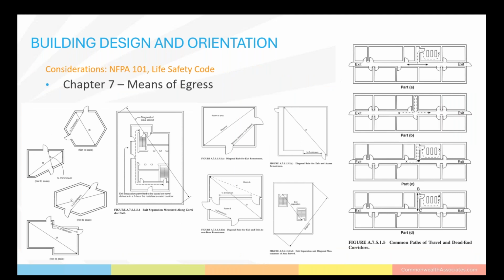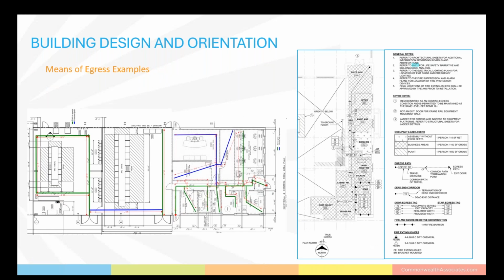Also mentioned earlier, the NFPA codes for life safety. Those basic codes from Chapter 7, means of egress, that need to be met are safe and quick exiting of the building. Exits must be located in accessible areas. Egress must be properly shielded from fire and smoke, ensuring occupants can safely evacuate. And finally, once occupants have exited the building, that there's a clear path to safety. Each of these two examples are individual pages from an overall life safety plan. Each shows the clearest path and distances to safe exits, to verify all the distances are within code requirements. The example on the left shows the basics of an office space and control room area and its attached electrical room that I'll talk about a little bit later. The example on the right has similar route paths shown, as well as expanded data, including occupancy load areas.